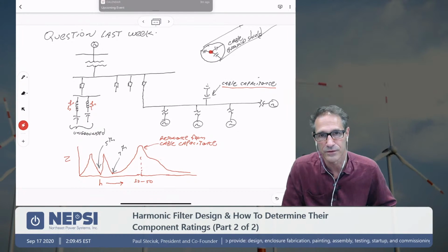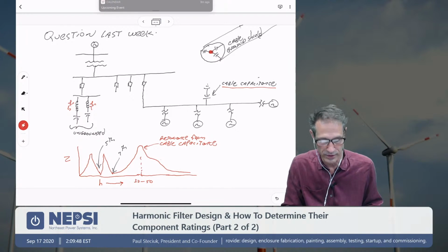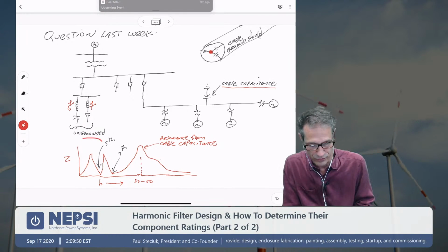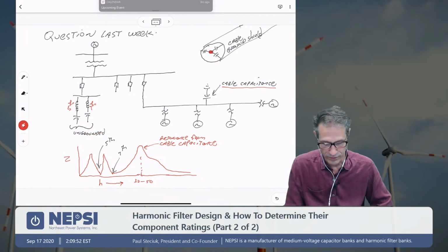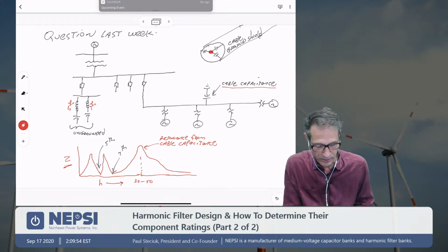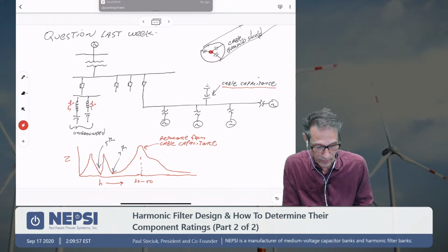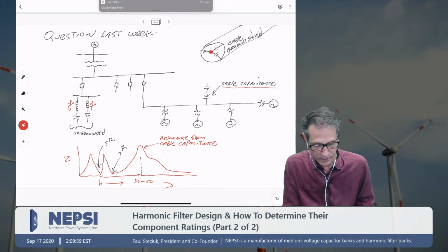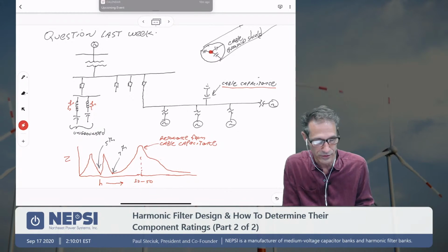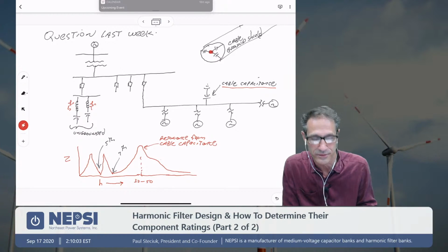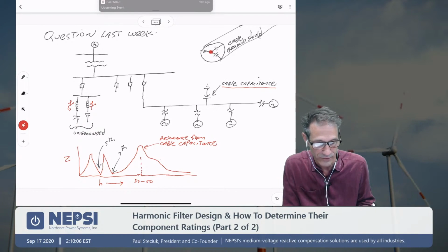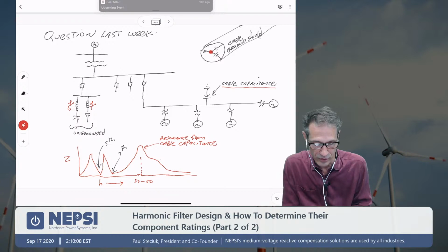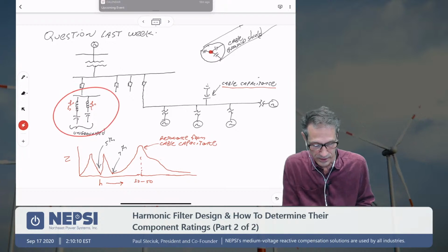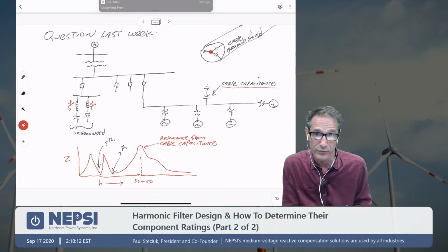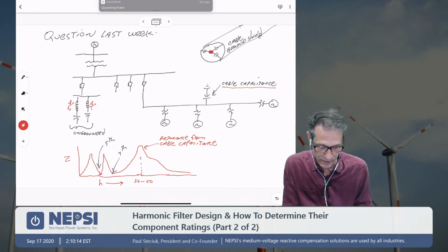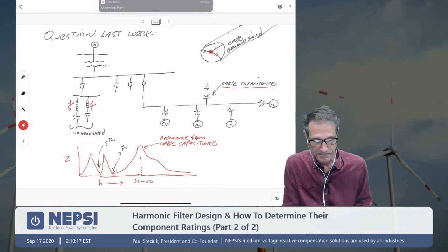It does enter into the resonance calculations, and it's really the balanced portion of that capacitance that's going to make it into the resonance. So down here I drew an impedance curve for the system, and I have a Z here, harmonic number here in this direction. And typically that cable capacitance is usually maybe a megavar on a typical wind farm, or 2 megavars at most. When you have a harmonic filter system installed, in this way I have a 5th and a 7th, so we know that because of the low impedance that exists here at the 5th and here at the 7th.